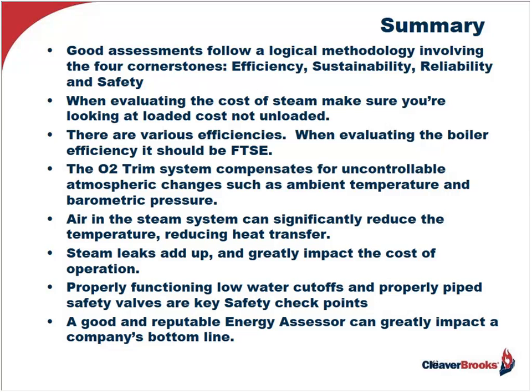Properly functioning low water cutoffs and properly piped safety valves are key safety checkpoints that the assessor will be evaluating. A good and reputable energy assessor can greatly impact a company's bottom line.